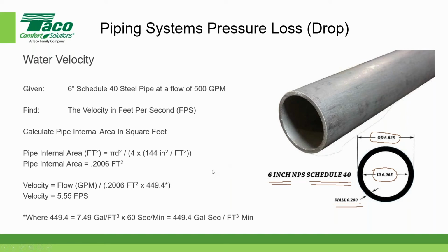And that's where the 449.4 comes from: 7.49 gallons per cubic foot times 60 seconds per minute. It comes out to a constant of 449.4. And the units, believe it or not, are gallon-seconds per cubic foot-minute. I'm sorry, per cubic foot-minute.